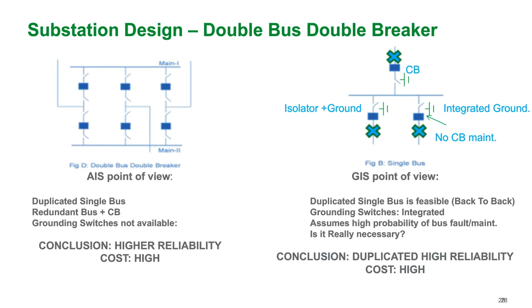And I'll go back again to that same logic here, that because we're not having to do maintenance on the switchgear routinely, because there's such a low probability of faults in gas insulated switchgear, we can propose a single bus as an alternate to this, just because you don't need the duplicated high reliability of switchgear. So if you do choose to do a double bus, double breaker arrangement with gas insulated switchgear, it can be done in many cases, and the cost is also very high.